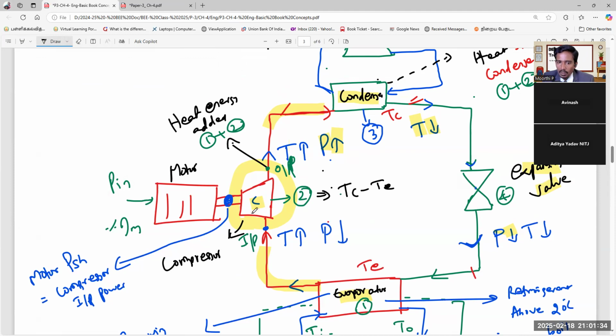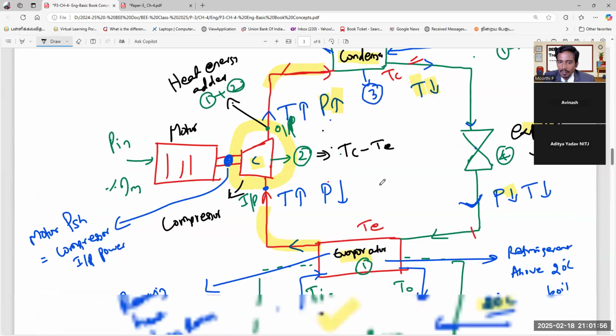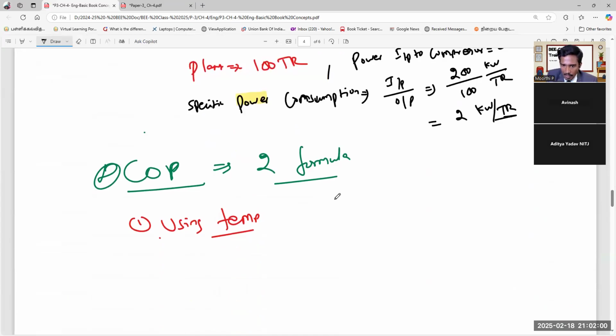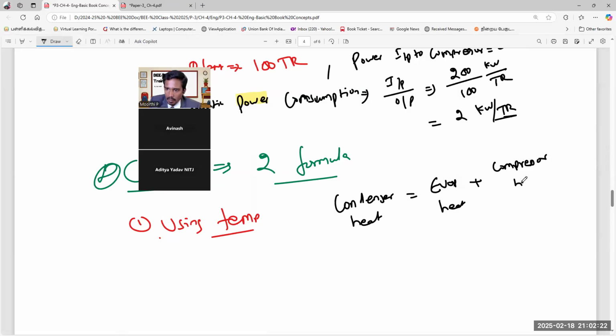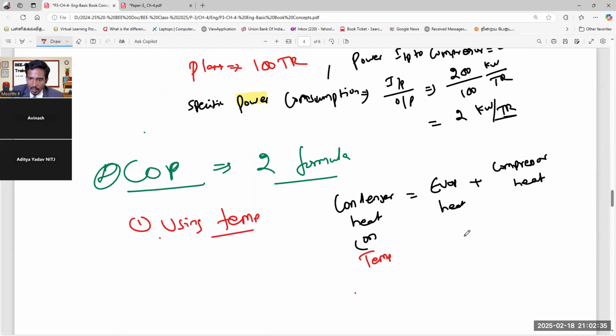The condenser heat load equals compressor heat plus evaporator heat. Are you right? Do you understand? Yes, the condenser equals the evaporator plus compressor. Now I need compressor, so it's condenser minus evaporator. That's finished. Always remember: condenser heat equals evaporator heat plus compressor heat.